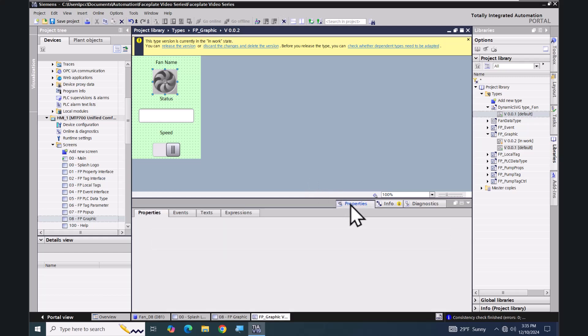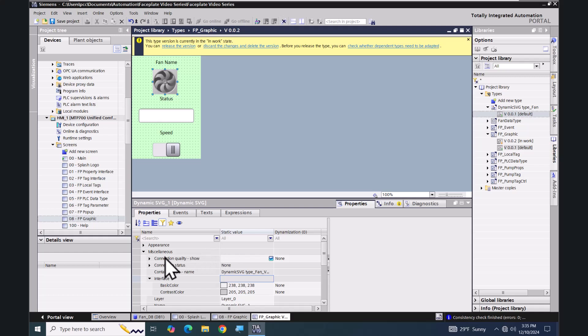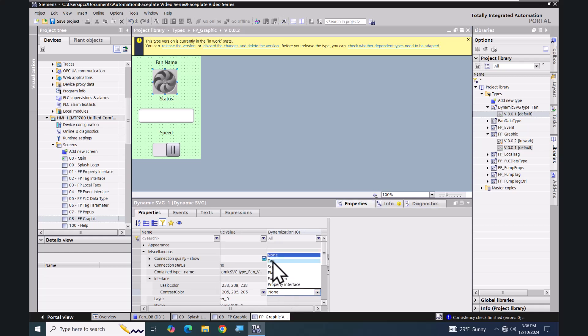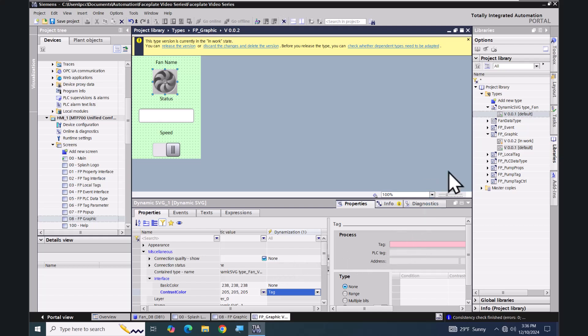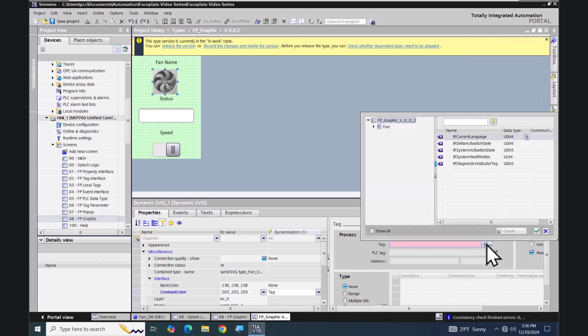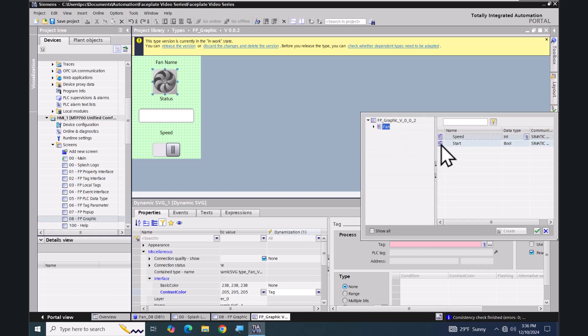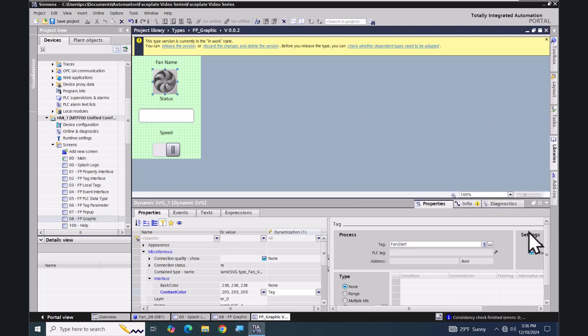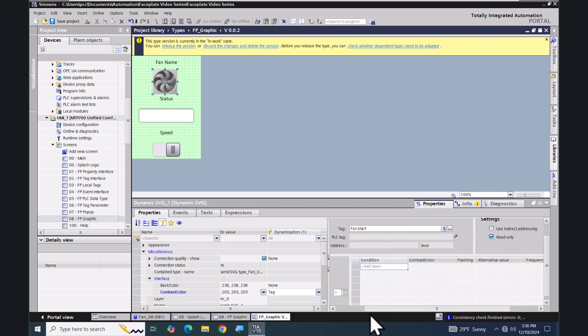I'm going to select the properties for the dynamic SVG. Under miscellaneous in the interface area you can change the basic color or the contrast color. I'm going to change the contrast color. I'm going to select a tag, minimize the libraries tab, and browse for my tag. I'm going to select fan and then the start element, and I'm going to do a range animation. I'm going to add in a condition — the condition is going to be one — and the contrast color is going to be green.